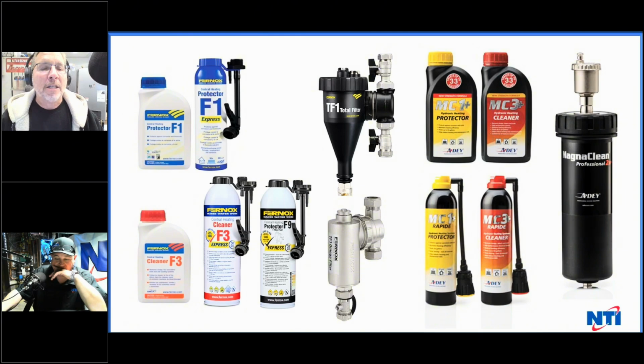So Malik asked a question: why should he put the magnet on the return? Because on the return, it will keep all the crud from getting back to the boiler and the boiler circulator, and it'll also keep it from getting to your circulators on the supply. That's why you put the magnetic filter on the return. If you have it on the supply, will it work? Yes. It's better on the return. You can put it on the supply, but it's better on the return.